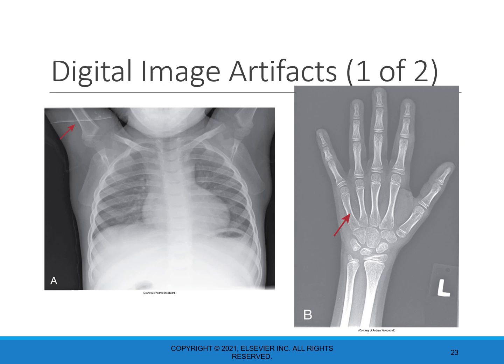Here you can see these tiny little spots. These are common little spots on a CR system when there's a speck or a lost area of phosphor, or of the barium fluorobromide. If there's a scratch or a ding, then there isn't any capture element left, and then you'll end up with these brightnesses that are artifactual.